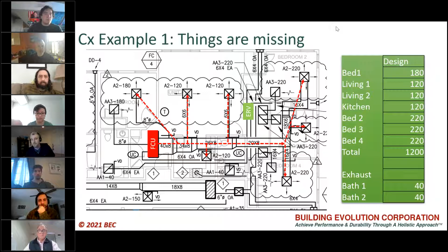This unit's bedrooms were reporting they're cold—they don't reach temperature during wintertime. So we had the TAB reports and the drawings of the building, and we went in to see what's going on. Unfortunately, the only thing you can see are the diffusers in the ceiling—it's all a gypsum, hard lid ceiling. So what do you do when there's a hard lid ceiling you can't see above? You get the hammer saw out and make some holes.